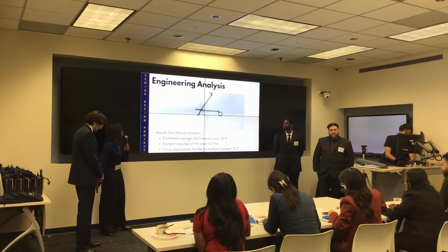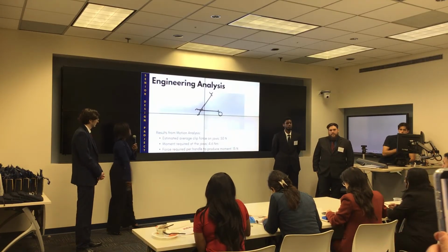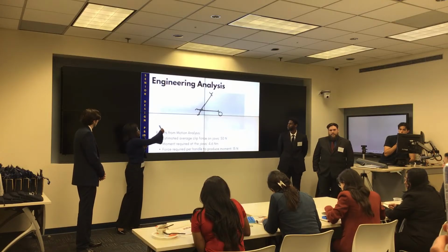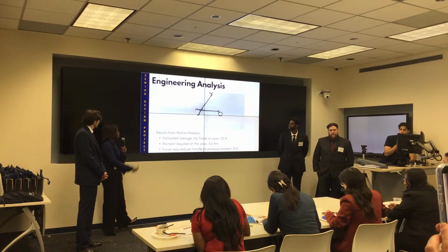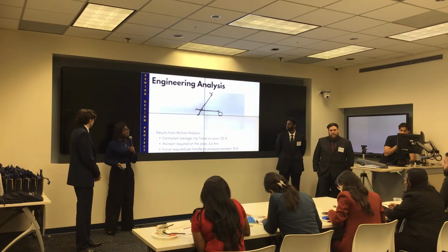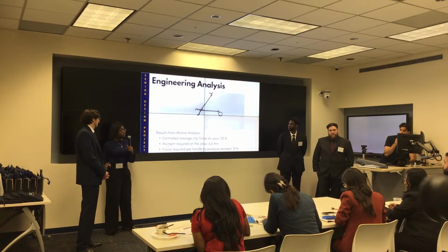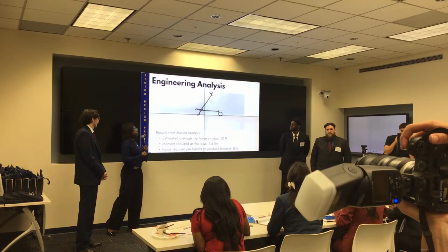So the first analysis that we performed was a motion analysis. We applied a motor at the pivot where our device moves, and we looked at a 50 Newton force at the jaws to simulate the force that the clips enact on the jaws as the jaws attempt to open the clips. With that, we were able to get an approximate moment at the jaws of 4.6, and we were able to use that to work backwards to get a value that the user would actually be using to open the clips: 15 Newton.